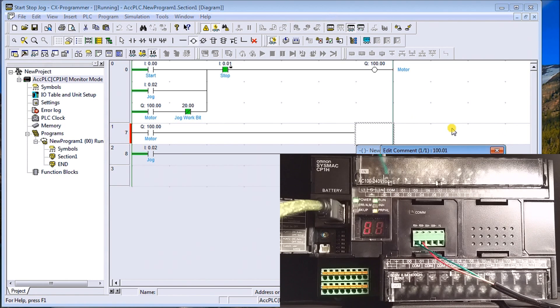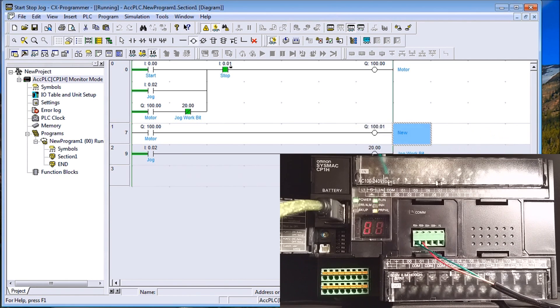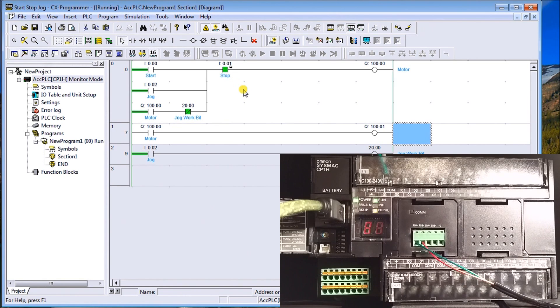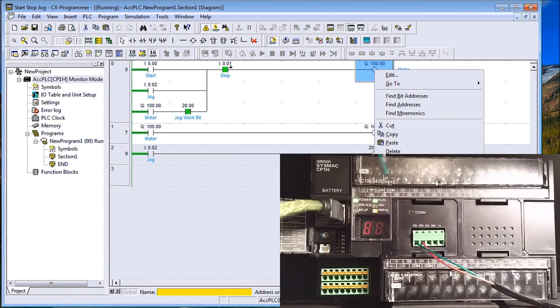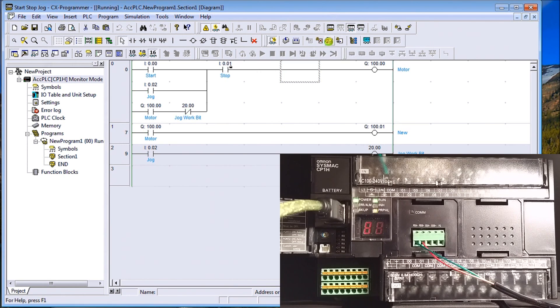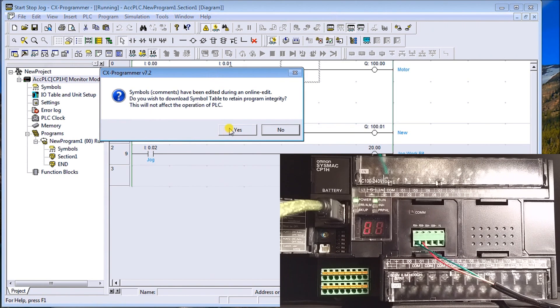We hit Control and arrow over to make our line, then place an output coil at address 100.01 — the next output next to our motor — with the comment 'new'. The completed rung has no red remaining, so we're good. From the icons I can cancel the online edit, send the online edit, or edit a specific rung. We'll accept all these rungs and send the online changes.